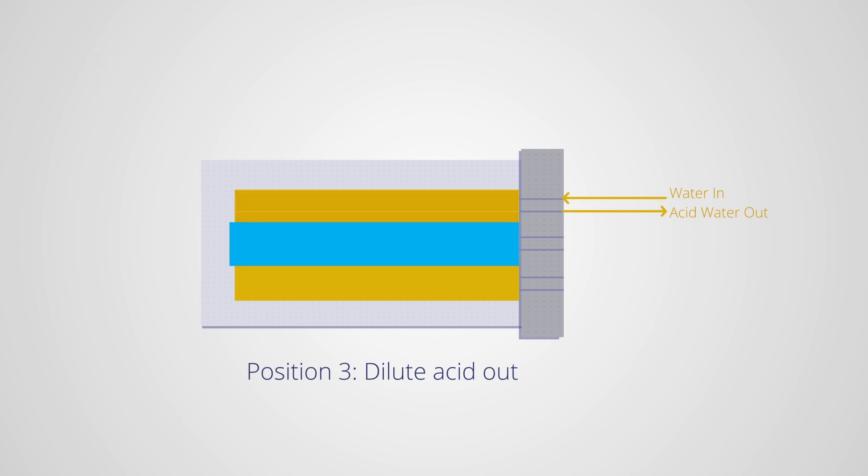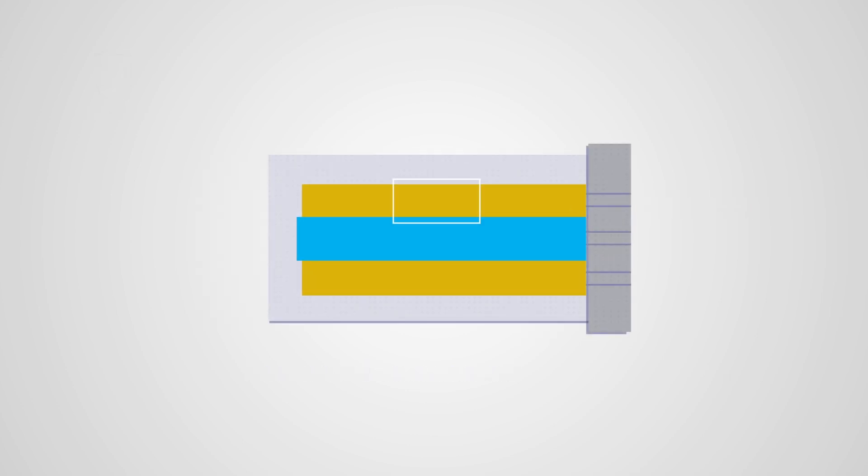Finally, in the last step of the suppressor process, the chamber moves to a third position, where it is rinsed with water to eliminate unbound protons.